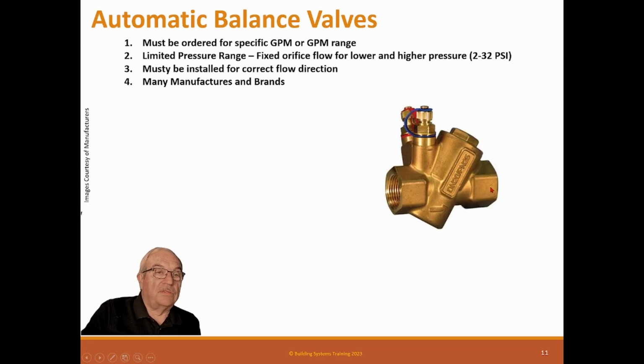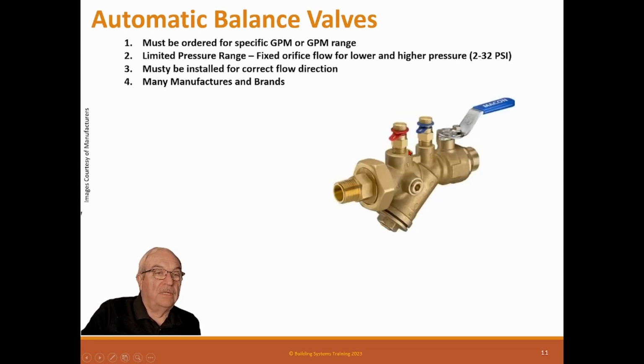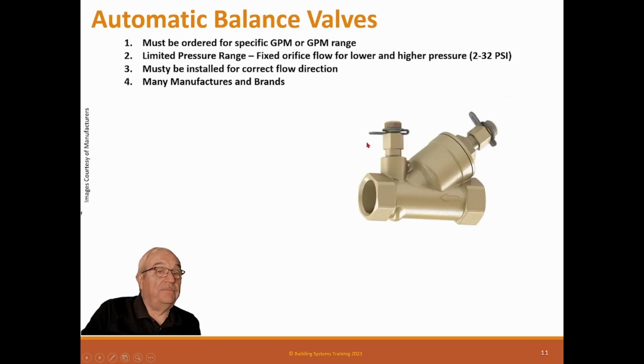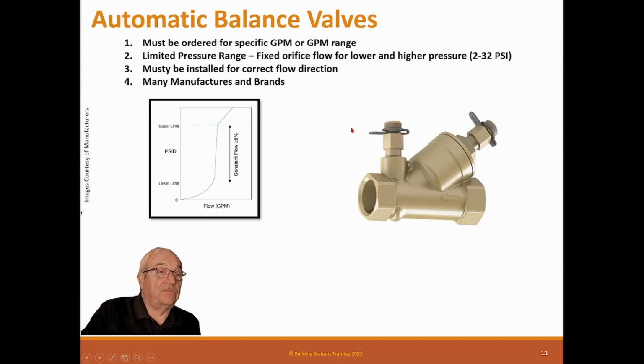This is another. This is Grundfos, I think, and this has a spring-mounted plunger this direction. Yeah, this is another one. This one actually has a valve. You'll see these all the time on the hose kits you buy. So this is the balance valve to change flow, and then our shutoff valve. And this is the automatic flow valve, but again, it has a limited pressure range. And this is another one that's pressure that you can actually read.